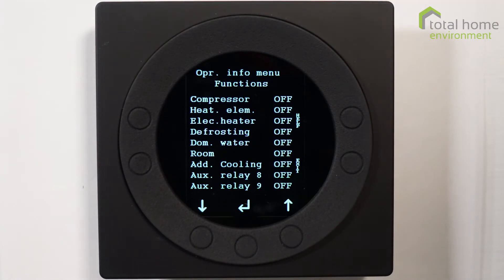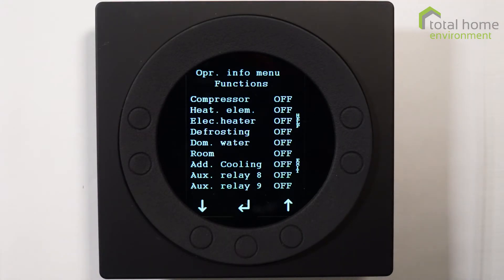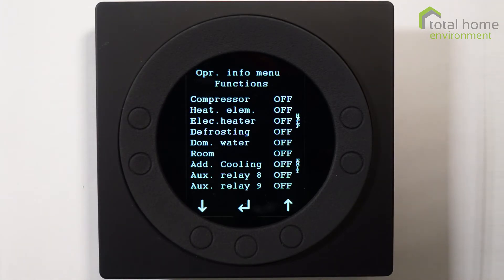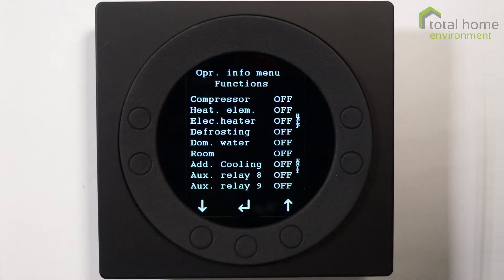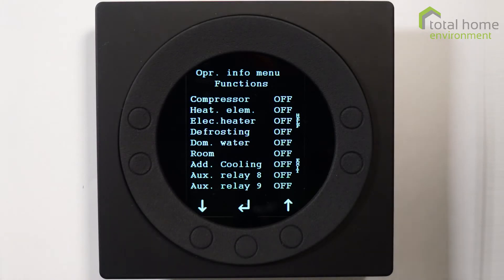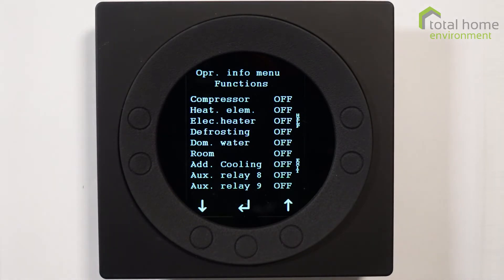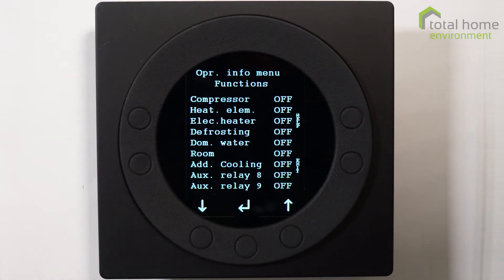When it is in defrosting mode, the supply air fan will stop. The reason for that is generally it gets very cold in that evaporator coil in the winter, and of course you don't really want to be blowing cold air into the property whilst it's defrosting. So the fresh air fan will stop, the supply air fan stops, just to make sure that the property doesn't cool too much during that defrosting period. It's an automatic function - once the coil reaches plus five degrees, it will go back to normal operation. It's entirely automatic and you'll probably not notice it at all.